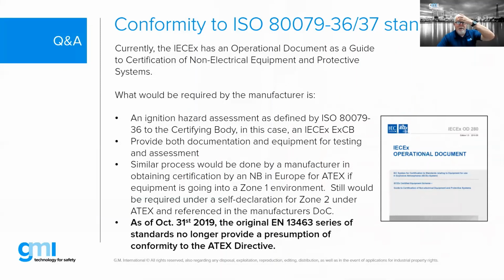So it's basically referenced in this IECEx document, this operational document. More or less what's involved is that there should be, in effect, an ignition hazard assessment carried out by the manufacturer, and that's what the 80079 standards entail. The manufacturer does an ignition hazard assessment, or leaves it up to the test lab to do that on their behalf. Or it can be done by the manufacturer themselves and reviewed by the test lab, and then a certificate is issued for it. One important thing: as of 2019, those old EN 13463 standards no longer provide presumption of conformity to the ATEX directive, so you would have to follow the EN version of 80079-36 and 37.